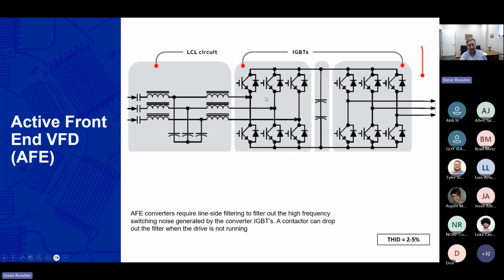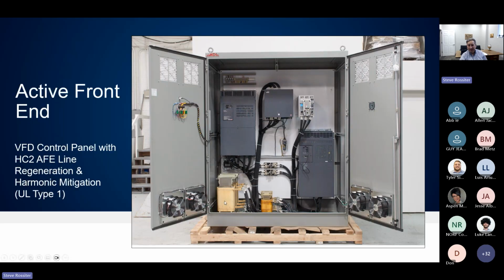You've still got that gulping effect, and you've still got power going through silicon, which now even gets a little bit more difficult to handle because the higher orders of those switching frequencies cause more problems in the EMI RFI area. Here's an example of this. That's how big that filter is for the LCL filter. So not a small device by any means.